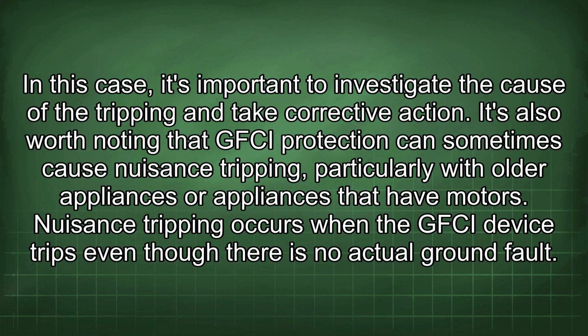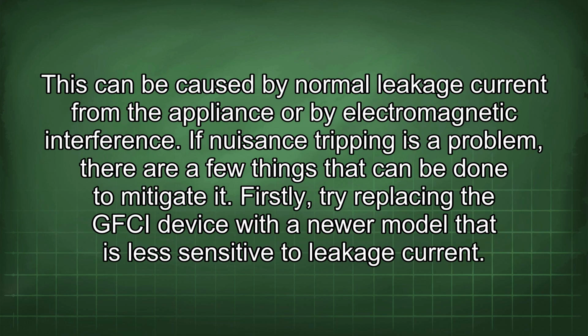It's also worth noting that GFCI protection can sometimes cause nuisance tripping, particularly with older appliances or appliances that have motors. Nuisance tripping occurs when the GFCI device trips even though there is no actual ground fault. This can be caused by normal leakage current from the appliance or by electromagnetic interference.